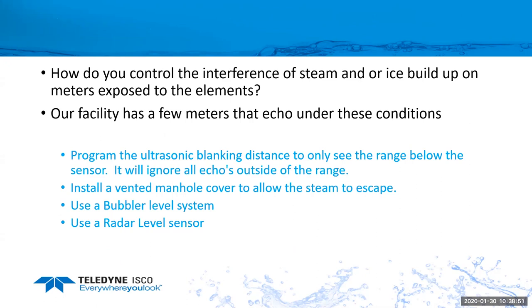So how do you control interference of steam or ice buildup on meters exposed to the elements? Our facility has a few flow meters that get echoes under these conditions. If you have the ultrasonic sensor, you could try setting the blanking distance on it. The default range is 0 to 10 feet. You can set that a little bit closer, so if it's getting stray echoes, it could filter or ignore the outside echoes. I've had people vent the manhole, so that instead of a solid manhole cover, it has grooves or vents in it to allow the steam to escape. Other options would be to go with a bubbler level system, because the bubbler would not be affected by wind or steam or foam on top of the surface. And another possibility is using a radar level sensor, because the radar sensor would be able to penetrate the steam and foam.